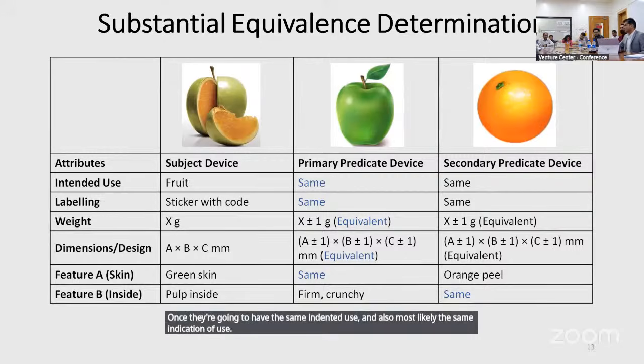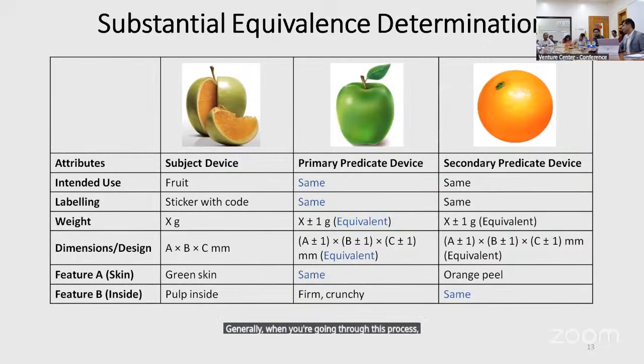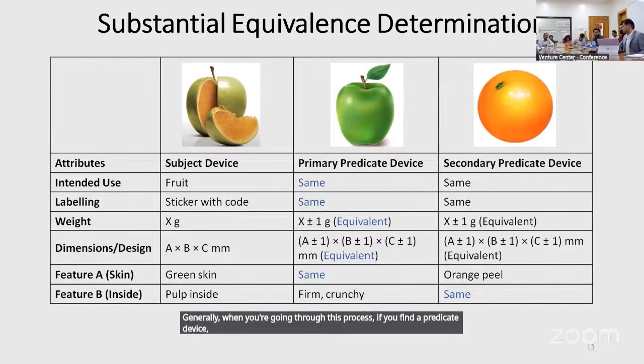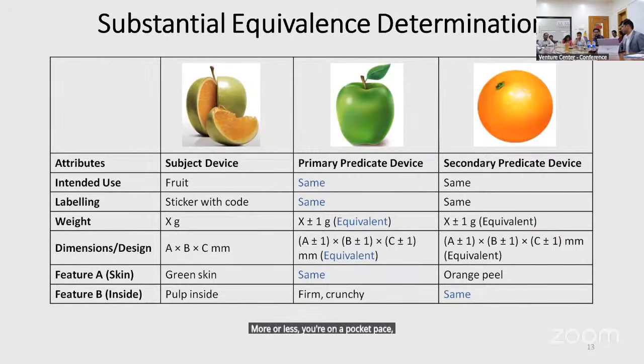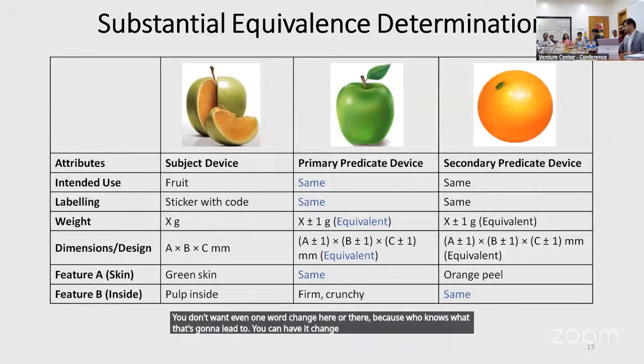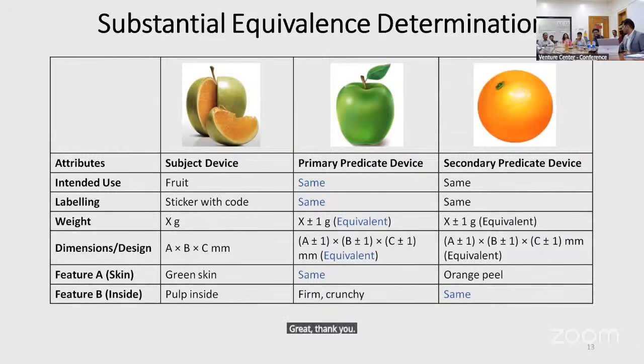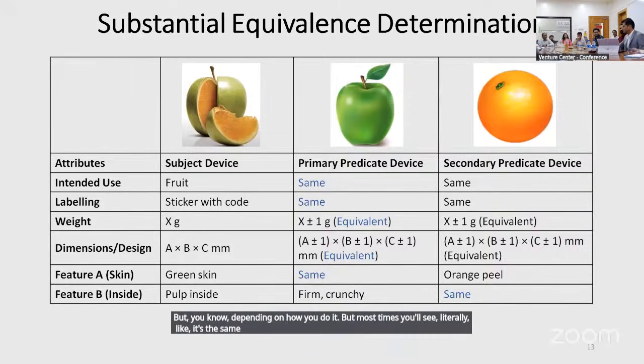So generally, when you're going through this process, if you find a predicate device, more or less you want to copy paste the indications of use. You don't want even one word changed here or there, because who knows what that's going to lead to. You can have it changed, of course, if you do it well, depending on how you do it. But most times you'll see literally the same indications of use being used again.